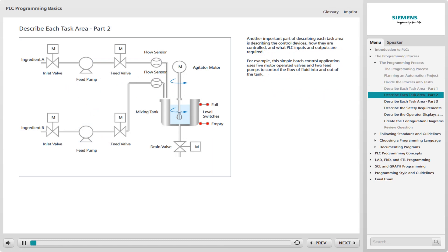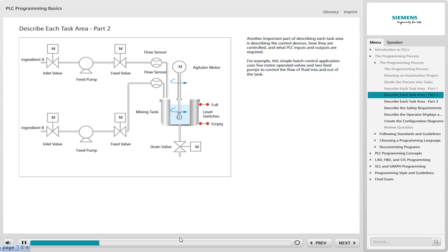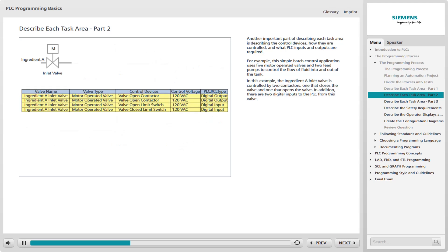Another important part of describing each task area is describing the control devices, how they are controlled, and what PLC inputs and outputs are required. For example, this simple batch control application uses five motor-operated valves and two feed pumps to control the flow of fluid into and out of the tank. There are a variety of devices that might be controlled.